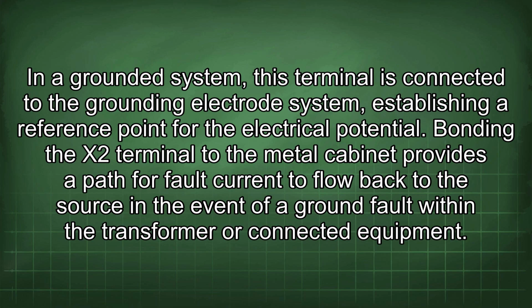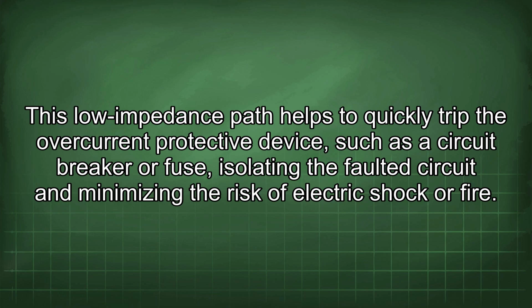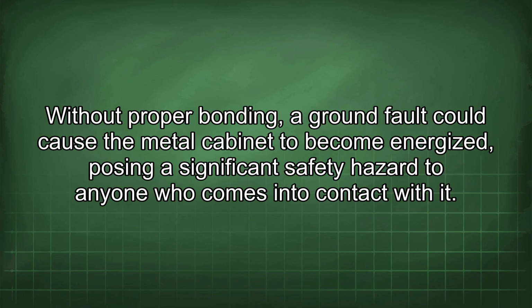Bonding the X2 terminal to the metal cabinet provides a path for fault current to flow back to the source in the event of a ground fault within the transformer or connected equipment. This low impedance path helps to quickly trip the overcurrent protective device, such as a circuit breaker or fuse, isolating the faulted circuit and minimizing the risk of electric shock or fire. Without proper bonding, a ground fault could cause the metal cabinet to become energized, posing a significant safety hazard to anyone who comes into contact with it.